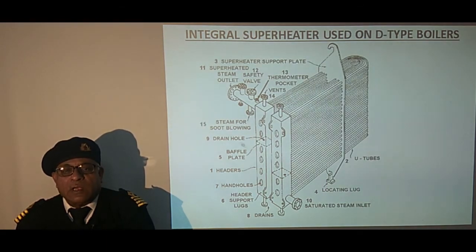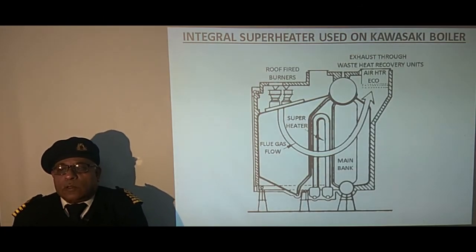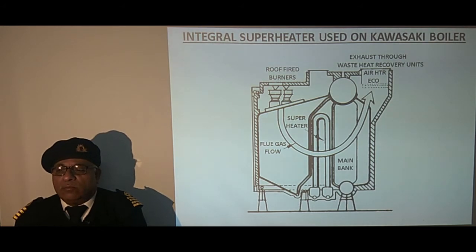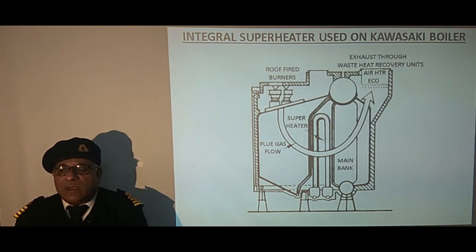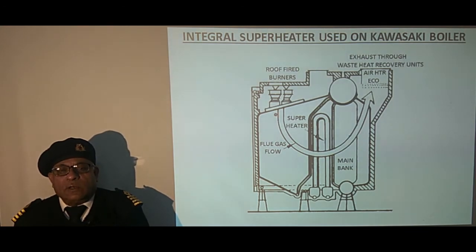Here we have a steam connection which comes out from the manifold for soot blowing purpose used in the boiler. This is a Kawasaki boiler which has vertically arranged superheater tubes parallel to the screen and generating tubes, attached to horizontally arranged headers at the bottom. This arrangement provides better drainage of condensate. In this modern boiler, the burners are on the roof and the flue gas passes over the screen tubes then through the superheater.